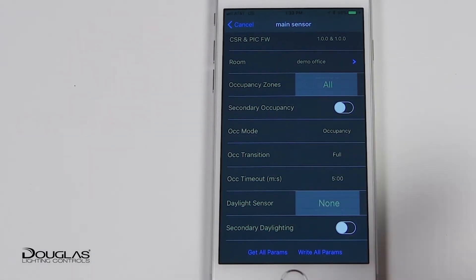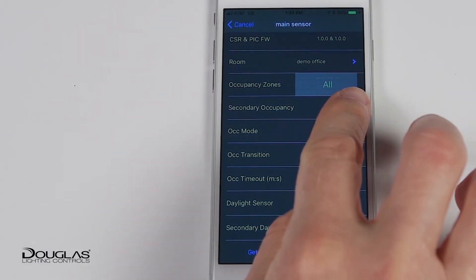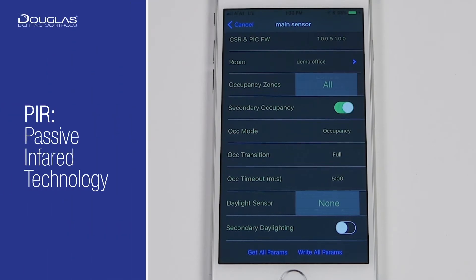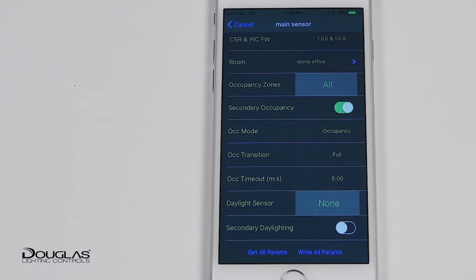Secondary Occupancy is Bluetooth proximity technology used for secondary occupancy detection. PIR, or passive infrared, is always the primary technology for occupancy. For a personal office, our wireless system can make use of the room control app and the Bluetooth proximity technology to maintain occupancy of that office when a person's iOS device is assigned and in that office.